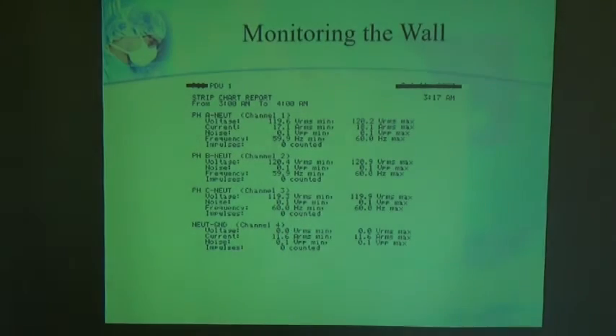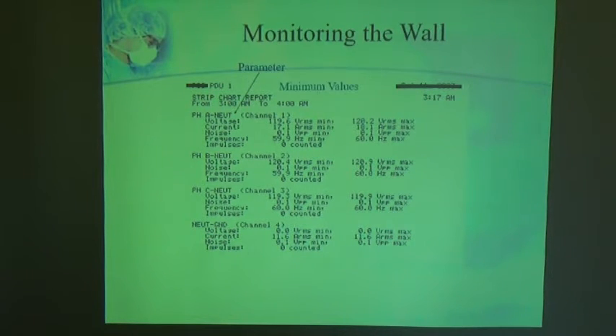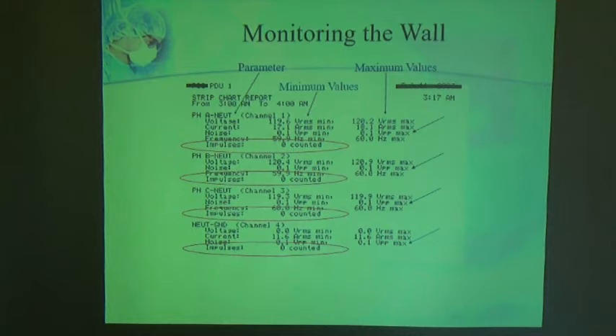This is a graph from an instrument that monitors the quality of power. There are 3 columns of data. On the left is the parameter of interest, the center is the minimum values, and the right column is the maximum values recorded during the monitoring period. What we see is 0 impulses and very low at 0.1 volts peak to peak high frequency noise. This is a 1-hour graph, but in fact, we would see the same results if we monitor this data center for a month or even a year.